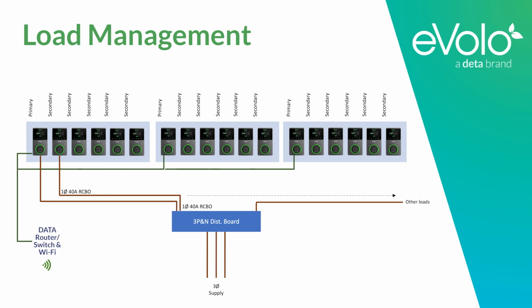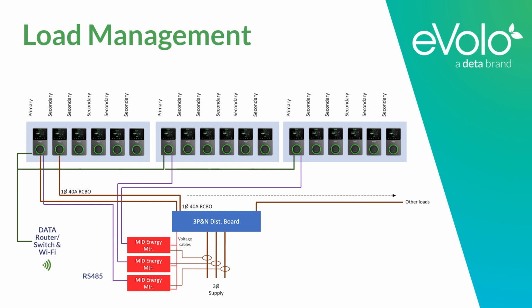alternatively over Wi-Fi. The additional hardware required in this scenario is energy meters, as they are needed to monitor the load on the supply. These may either be wired inline or using CT clamps, dependent on the meter used. RS485 data cables will be required between the energy meter and the primary charge point. The primary charge points will then monitor the total load, calculating how much power is available for the charge points and downrate depending on how many chargers are connected to ensure the supply is never overloaded.